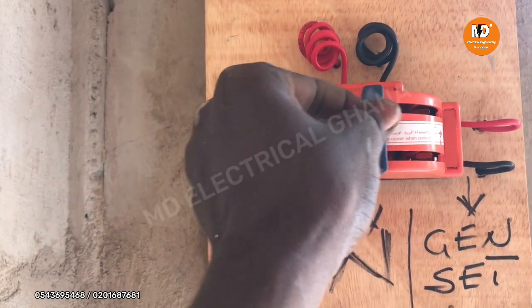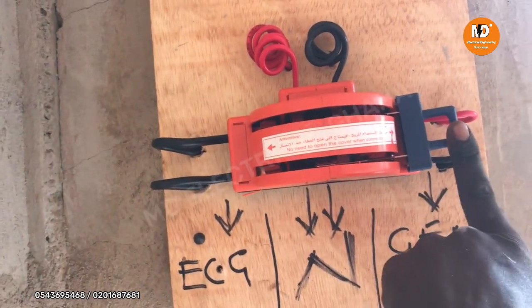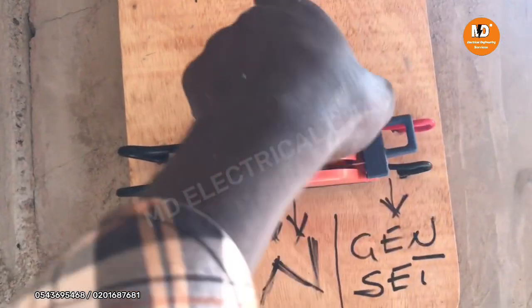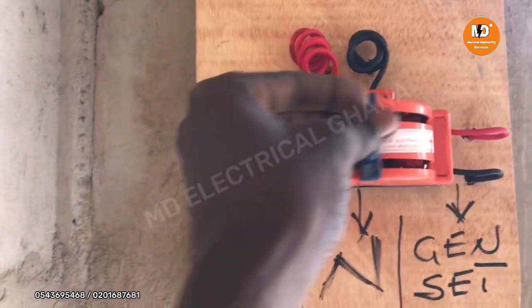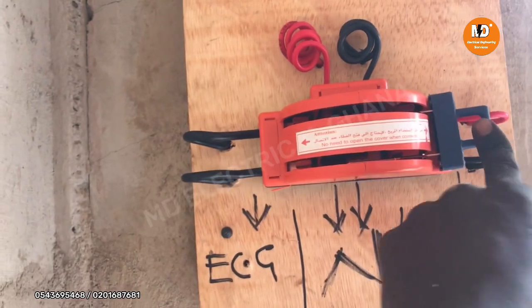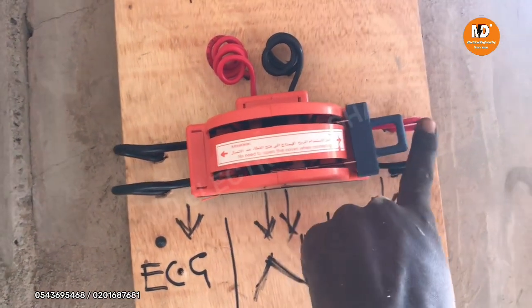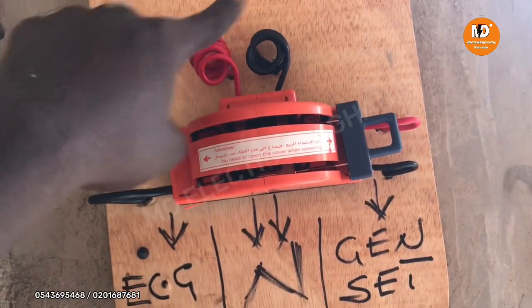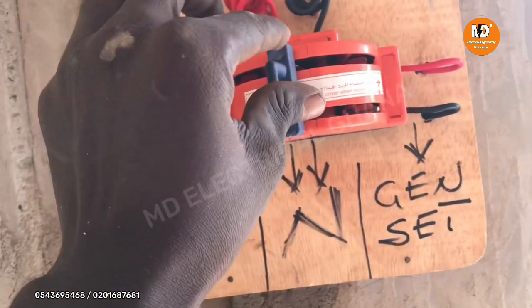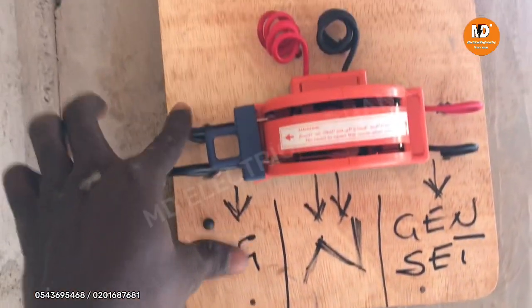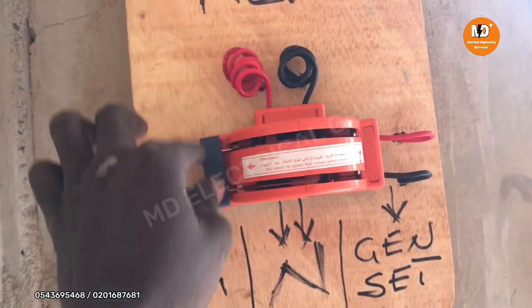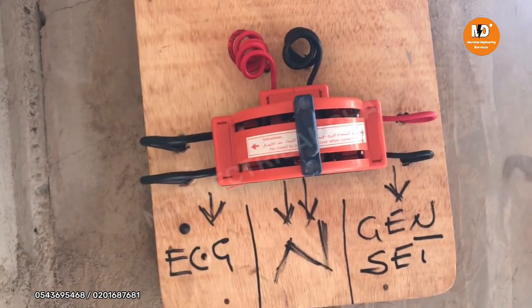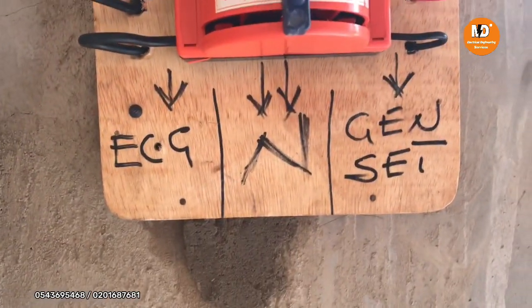So that's another demonstration. When there's a power outage from the ECG, you move the switch all the way to the generator set, and then you turn on your generator and you are good to go. And also, if there is power on the ECG side, you move to ECG. Power runs from the ECG position to the load and then to the distribution board, and vice versa.